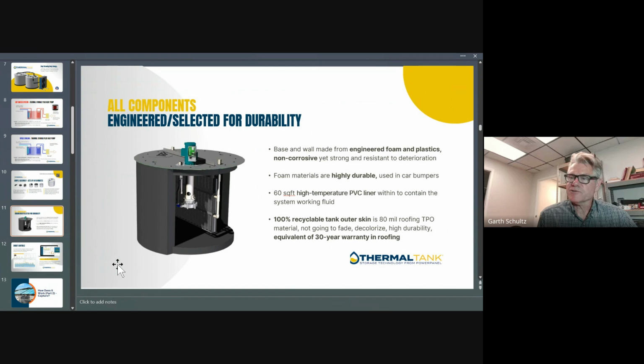It is an unpressurized tank. The volume that's holding the energy is exposed to atmosphere, so it doesn't have that pressurized fault built into the system. The only thing pressurized is the fluid within the heat exchanger set. Now, starting from the outside, the outer skin the tank is assembled of, and the top lid assembly, that's a common roofing material.